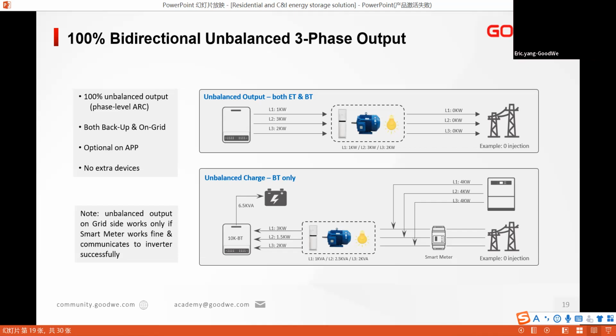I'll explain. For example, if the inverter is 10 kilowatts for three phase for our ET series, the maximum output of each phase is 3.3 kilowatts. So the maximum load is 3.3. If you connect a single-phase load with a consumption of 4 kilowatts, it only gets 3.3 kilowatts from the GoodWe storage inverter, and the remaining 0.7 kilowatts comes from the grid.